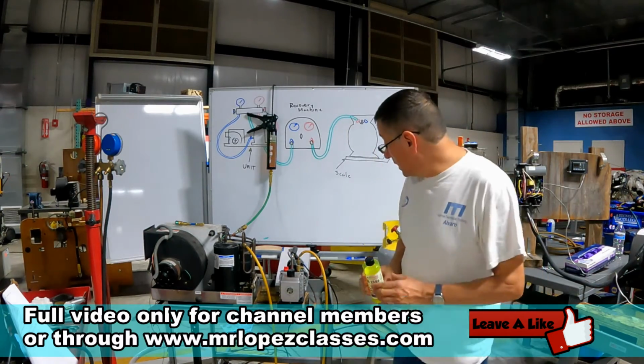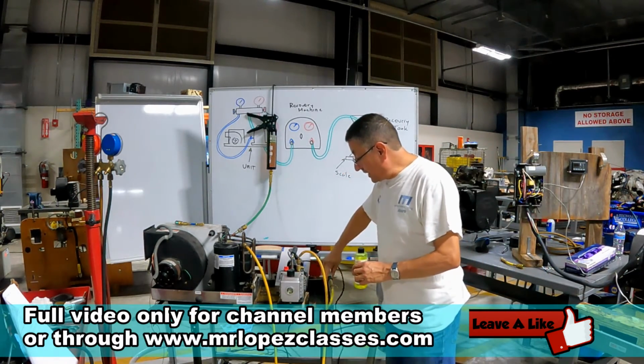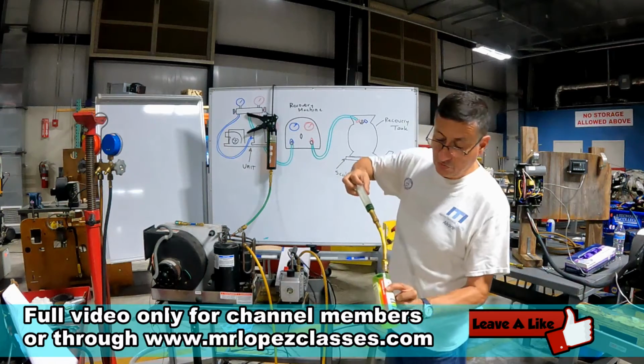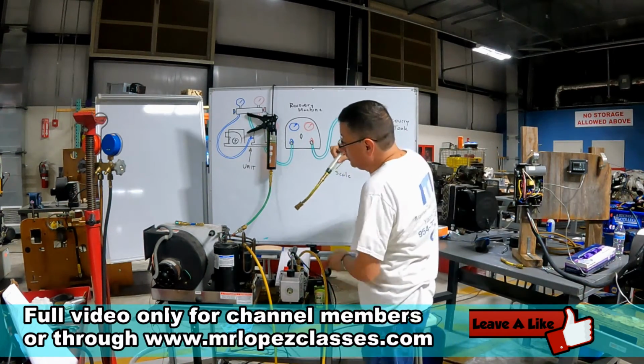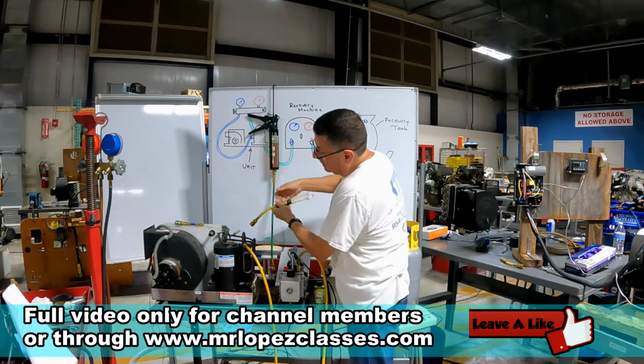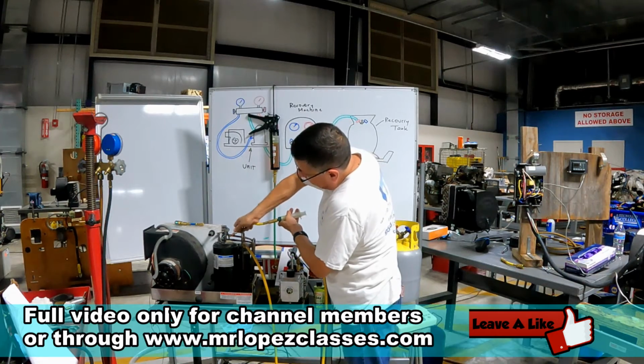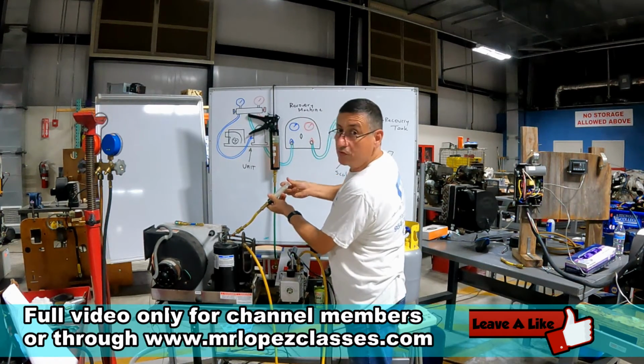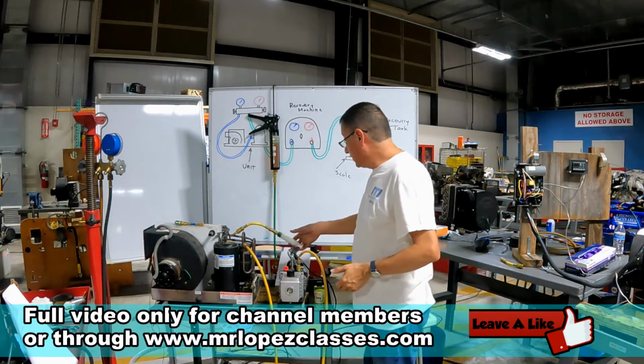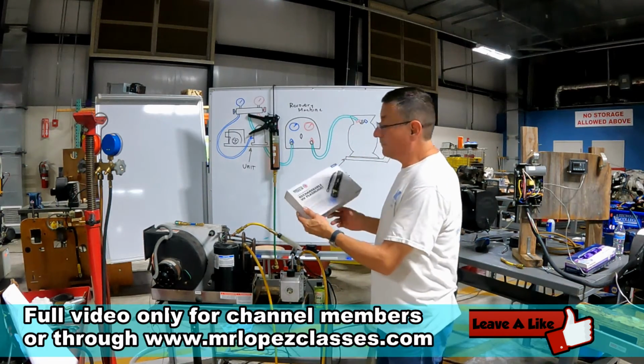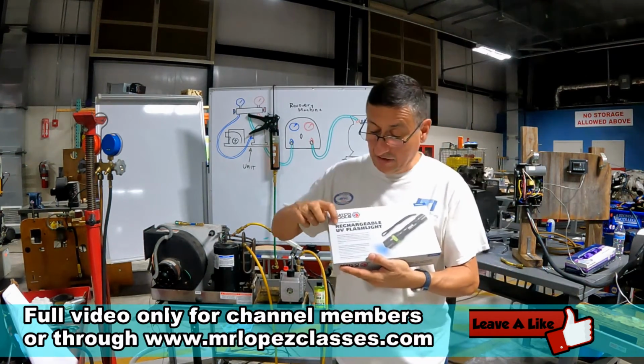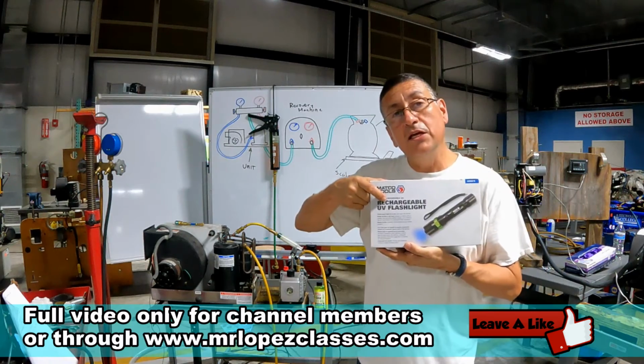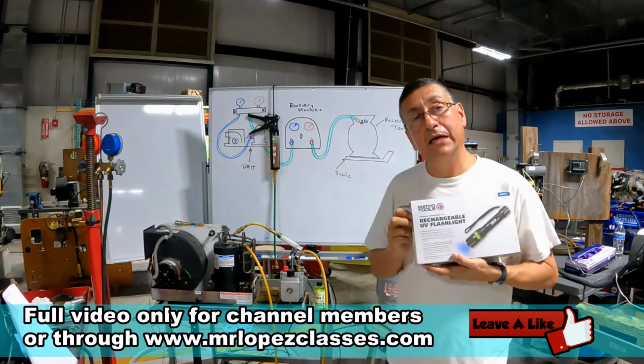I can verify the leak by introducing dye, the developer. How can I introduce the dye? There are different ways to introduce the dye. With this, you suction the dye, and you introduce the dye in the system. After that, with a flashlight, especially a UV one, you can determine where the leak is.